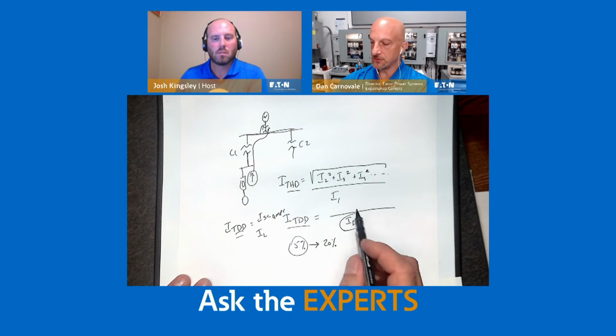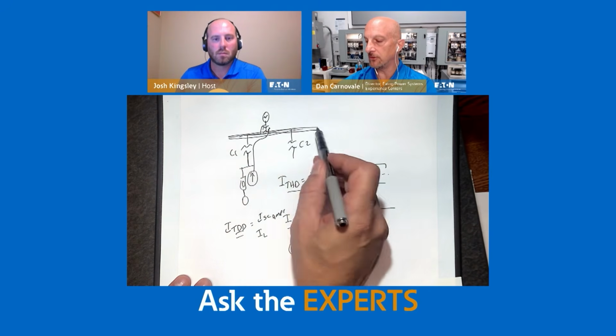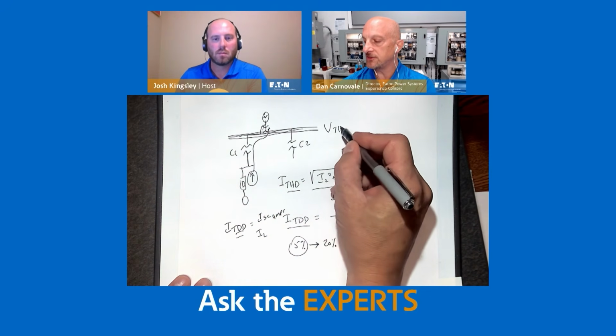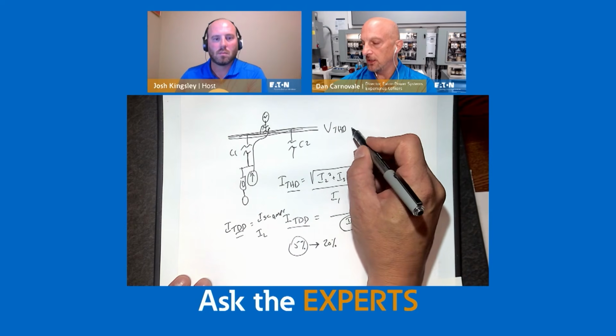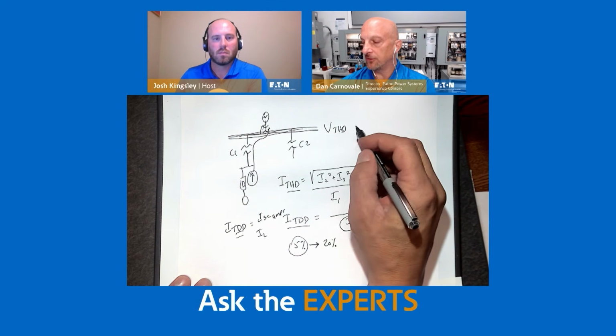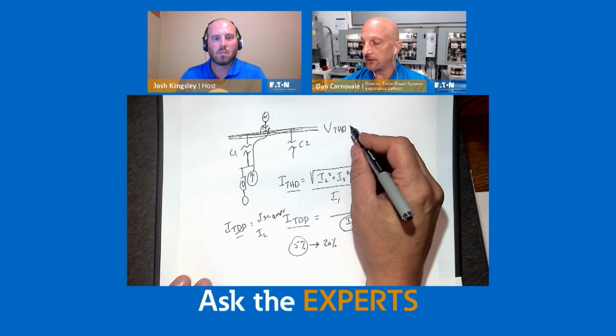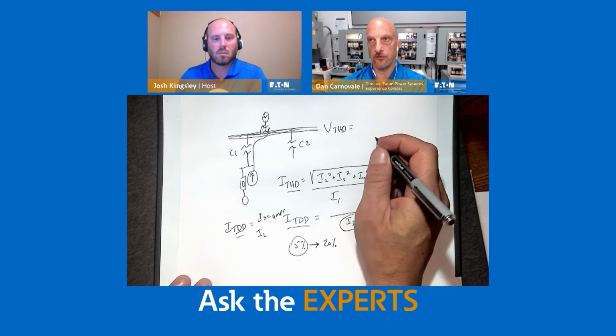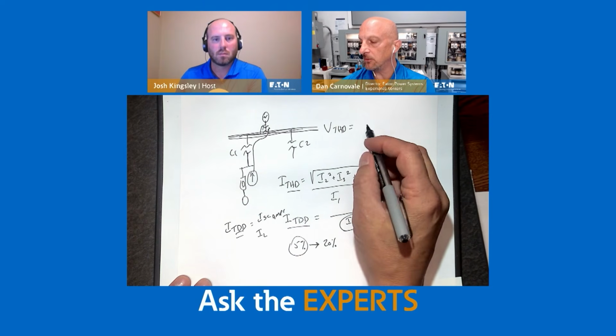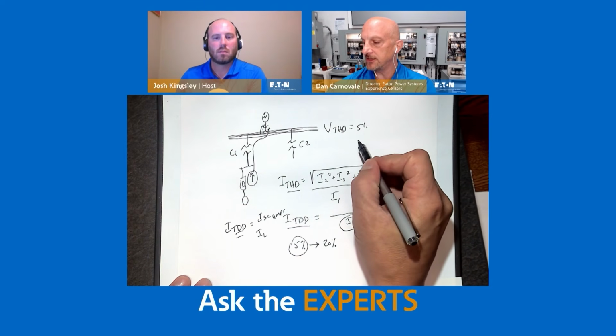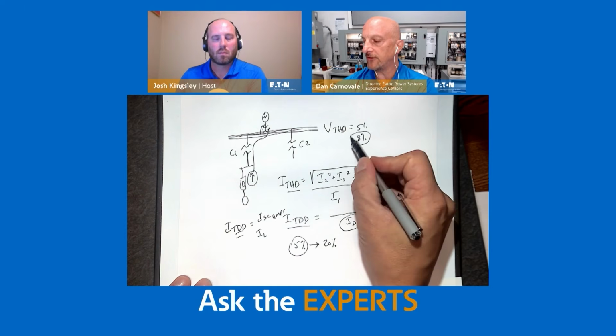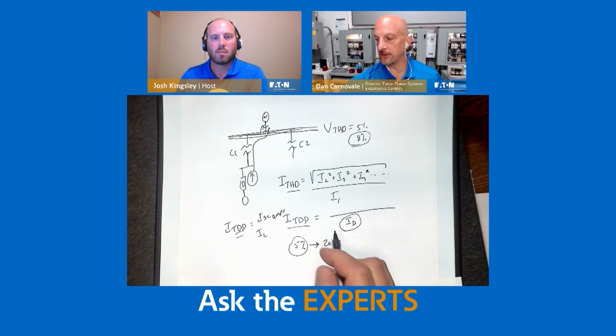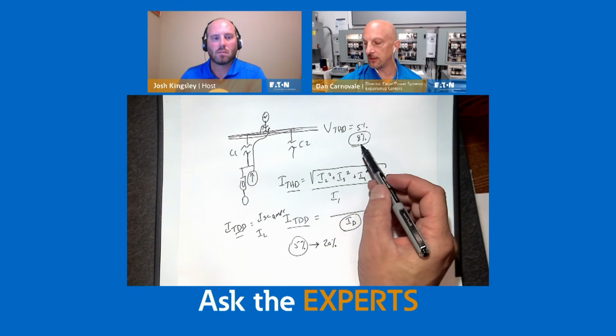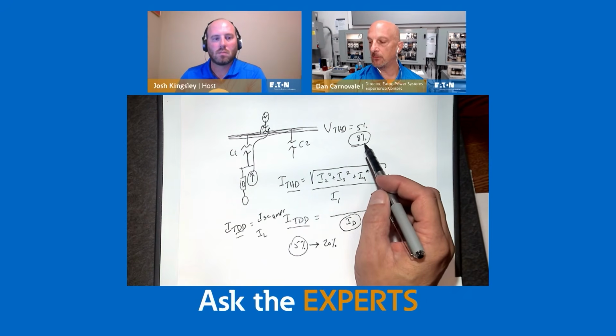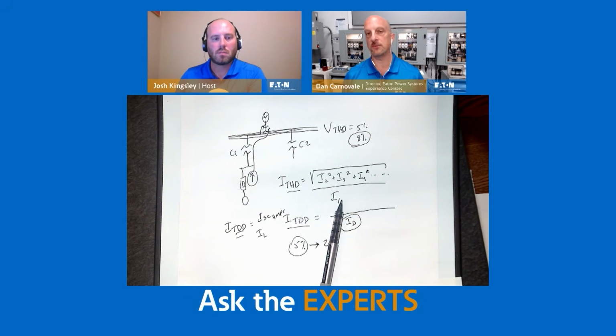But the voltage distortion levels, the part that it's really referring to more importantly, is VTHD here. Usually, that goes by voltage level. So if I'm at 480, for example, that's the one change that was made from 1992 to 2014, and it went from 5% THD to 8% THD. And what they found was you didn't have to be quite as clean on most power systems at 480, so you could allow a little bit more voltage distortion. But again, there's no magic number. So as soon as you get to 8.2% distortion, everything is going to start failing.